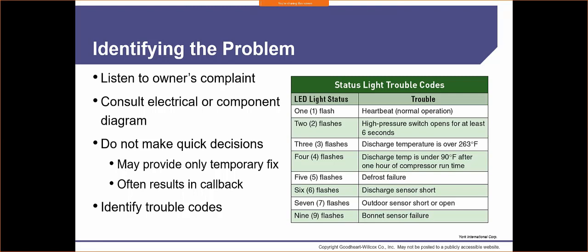There's a difference between a quick fix and a temporary fix. If I have a certain type of part that's going to get the system running until I can get back to the supply house tomorrow, and it's 11 o'clock at night, well, okay, I may hook up that part to make it work. I will never bypass any safeties. Safeties are critical to prevent a system from failure or a fire. So we never want to bypass a safety. We can bypass a safety for testing purposes, but I'm not walking away from that machine with a bypassed safety. Understand there are certain things I can do as a technician to make the system work until I can get the right part, but I always want to make sure that it's done safely.